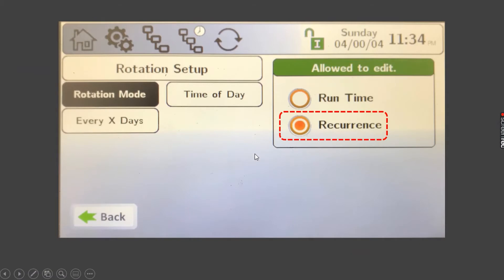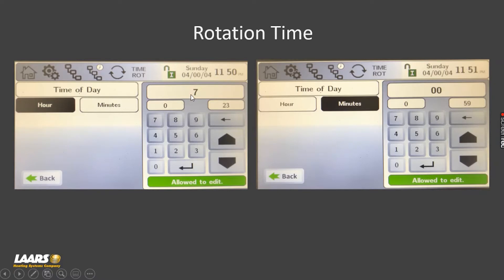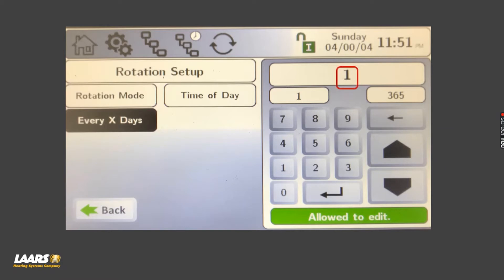Back to rotation setup, the other option under rotation mode is reoccurrence. Here you can actually choose the time of day — in this example the hours are set for 7 and the minutes for 00, so at 7 a.m. it would do its rotation. Then you choose how many days under 'every X day' — maybe every day at 7 a.m., or every two days, or once a week. In this example it would rotate every day at 7 a.m.